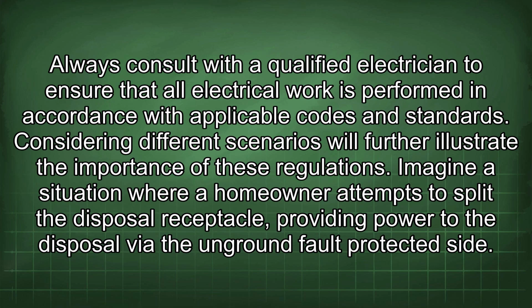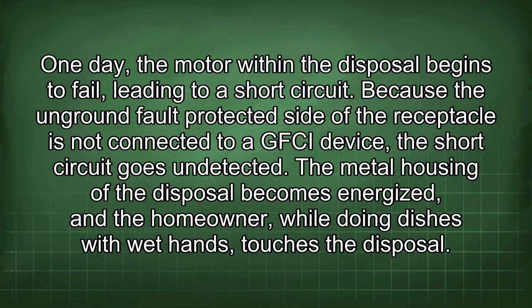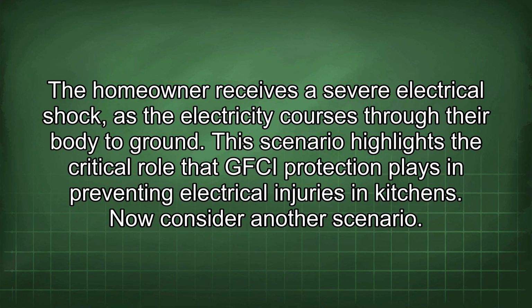Imagine a situation where a homeowner attempts to split the disposal receptacle, providing power to the disposal via the non-GFCI-protected side. One day, the motor within the disposal begins to fail, leading to a short circuit. Because the non-GFCI-protected side of the receptacle is not connected to a GFCI device, the short circuit goes undetected. The metal housing of the disposal becomes energized, and the homeowner, while doing dishes with wet hands, touches the disposal. The homeowner receives a severe electrical shock, as the electricity courses through their body to ground. This scenario highlights the critical role that GFCI protection plays in preventing electrical injuries in kitchens. Now consider another scenario.